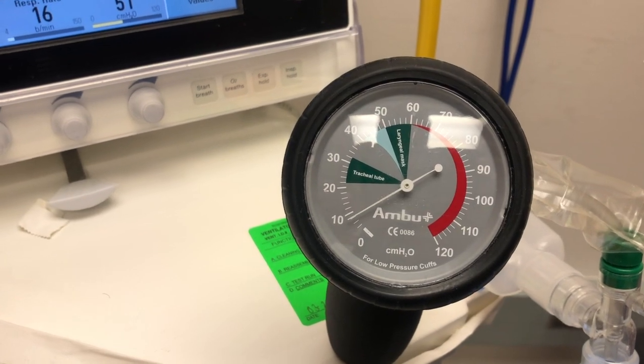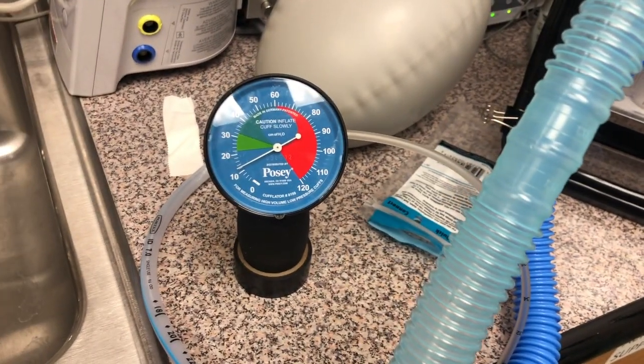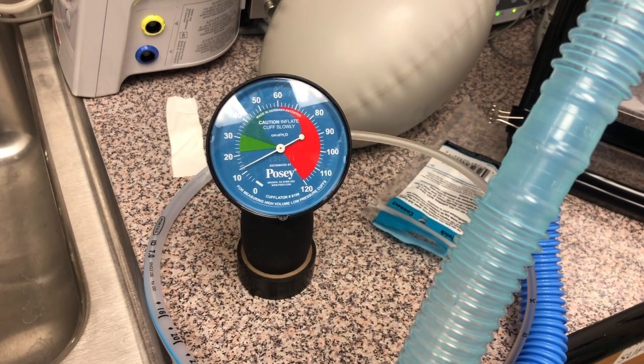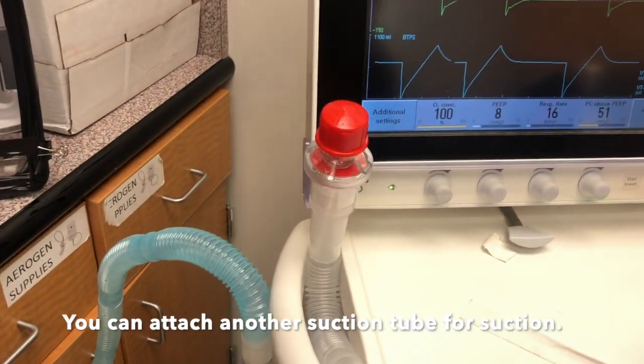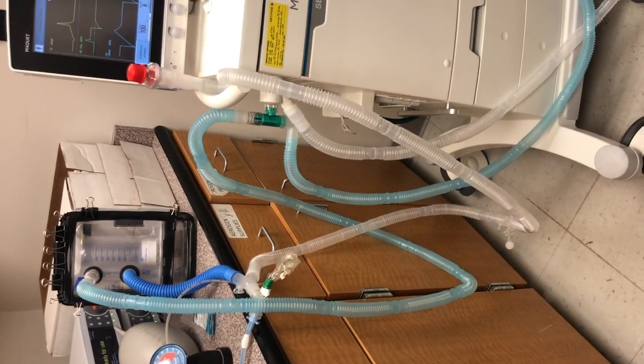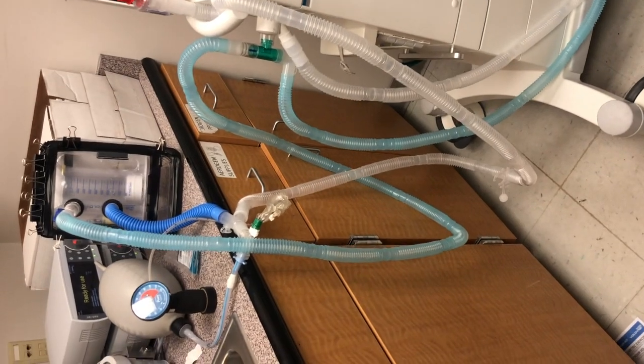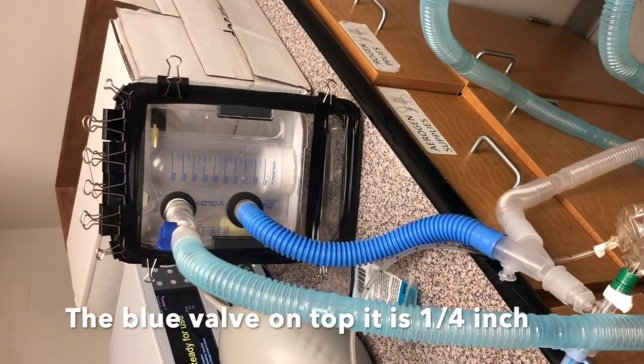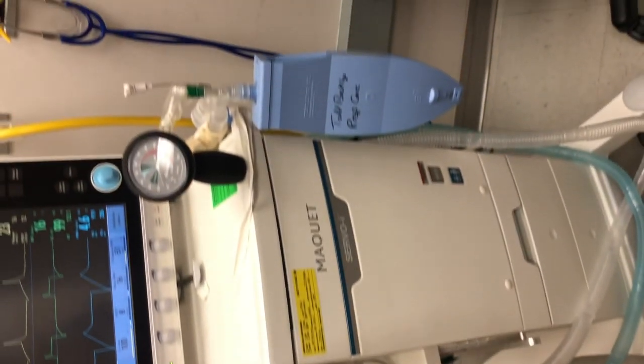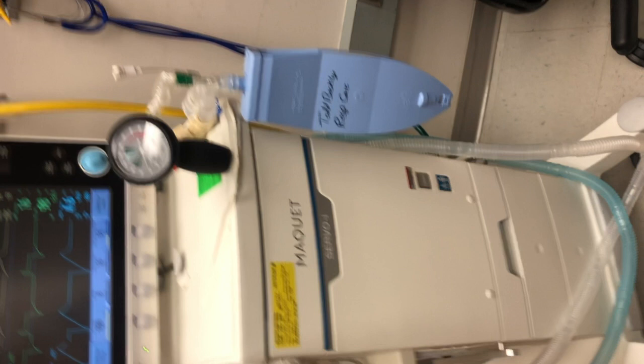The cuff pressure meter, which is readily available with respiratory therapists to measure cuff pressure, is connected by hooking it directly into the suction tubing and measures PEEP and peak pressures in real time. There is a valve in the inspiratory limb which is used to modify the volume or pressure, whichever is needed in each individual patient according to need. If you look at the other lung, the inspiratory limb is again connected to a ball valve, which is connected to suction tubing and to the ventilator. The suction tubing is again connected to the pressure gauge meter. This is the simplest setup for the second lung, which can give individual pressure control ventilation without affecting the other patient in real time.